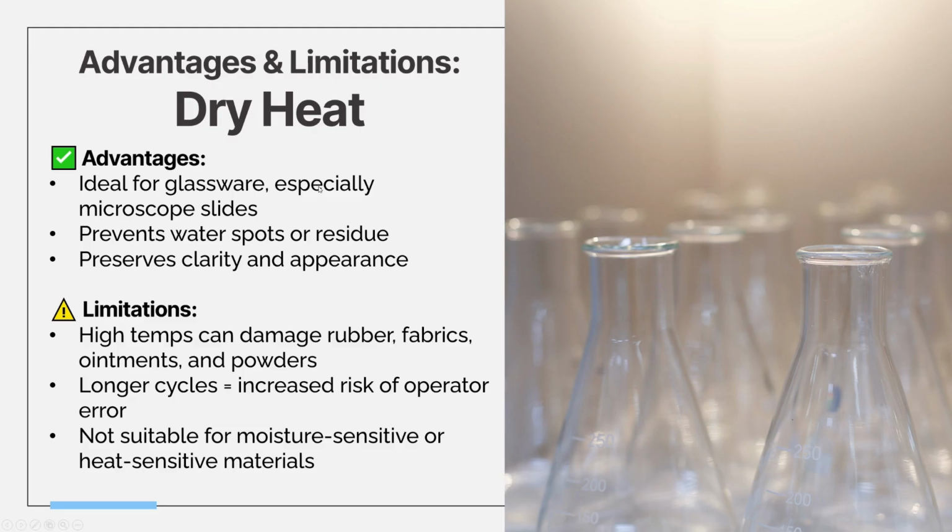So advantages include suitability for glassware, as I mentioned, no water spotting, and preserving appearance. But limitations include incompatibility with other sensitive materials, extended cycle times, and higher risk of user mistakes as a result. You always have to weigh the pros and cons depending on the material being sterilized.